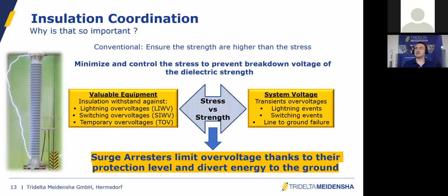I'm going to accelerate a little bit to make sure I respect the time frame. A very important topic is the insulation coordination for such arresters. You're going to tell me it's obvious. Yes, it's obvious, because this is the main job of the arrester. But there is still a misunderstanding that we see in a few countries, for different projects, when we configure such arresters: there is often a requirement to have the same BIL for the surge arrester as the system. This is a kind of misunderstanding, because surge arresters protect the equipment, but they also protect themselves.